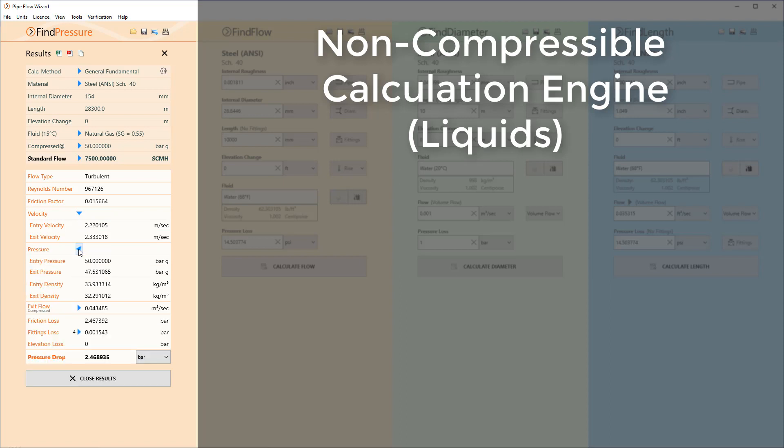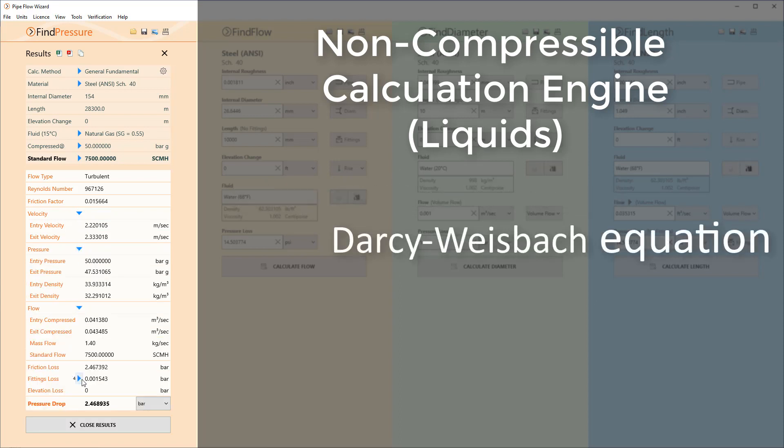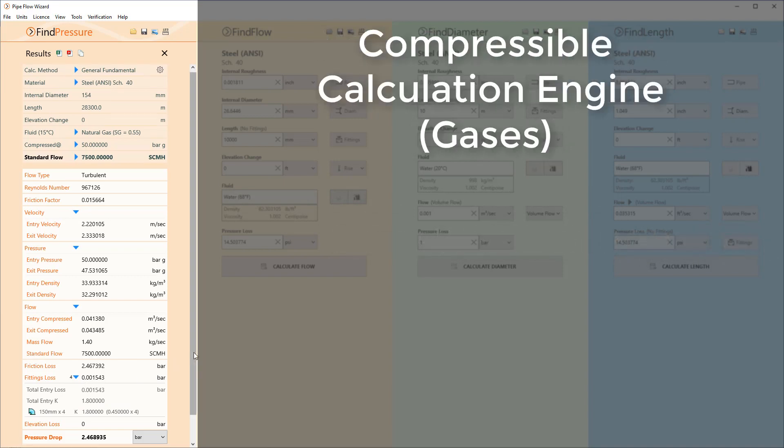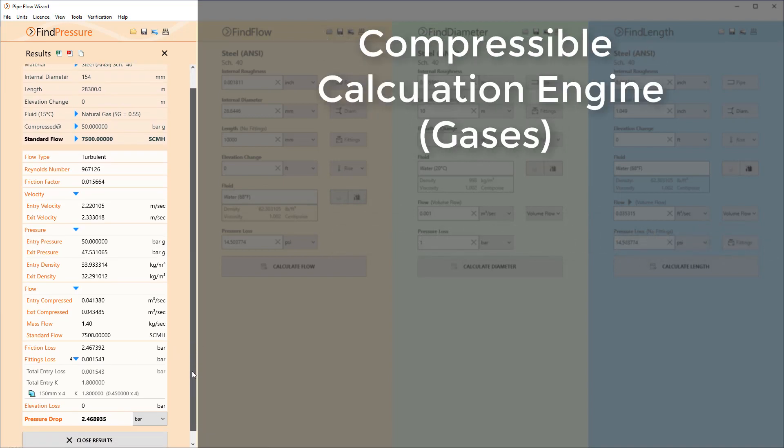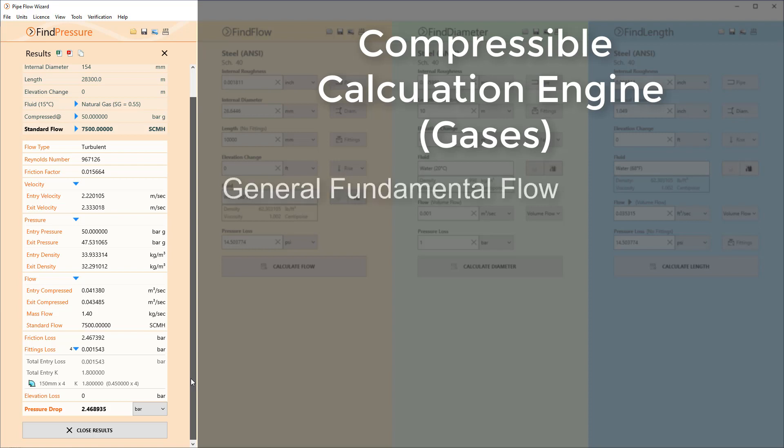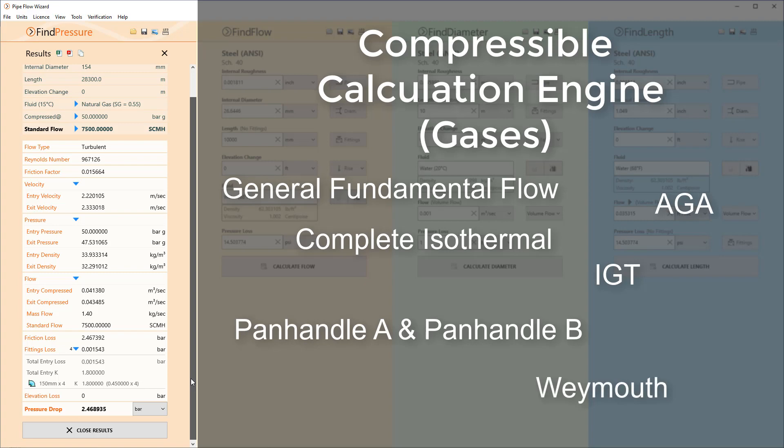The software contains a non-compressible calculation for liquids based on the Colebrook-White friction factors and the Darcy-Weisbach equation. It also includes a specialist compressible isothermal gas flow calculation engine with the ability to calculate results using the general flow, complete isothermal, IGT, AGA, Panhandle A and B and the Weymouth equations.